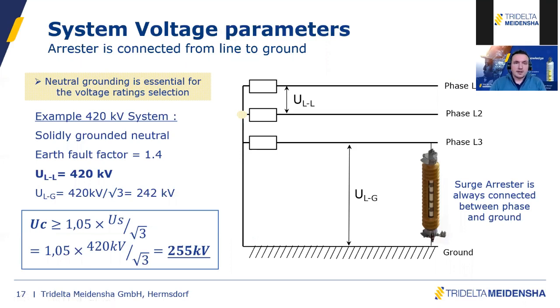I will give you a typical configuration. It's always difficult to go into the details, otherwise we would need 2 hours only to talk about voltage ratings, and this is not the purpose today. I'd like to give you an example for a 420 kV system with a solidly grounded neutral point. This is important. The neutral grounding system is also a key point for the voltage rating selection of the arrester.